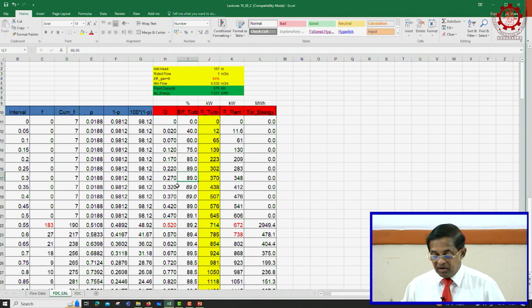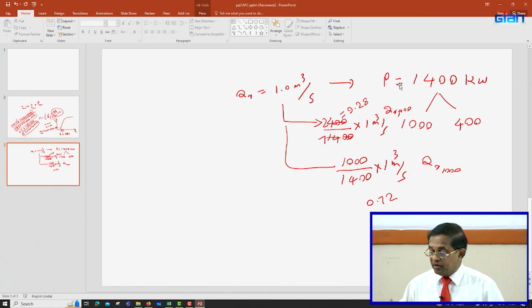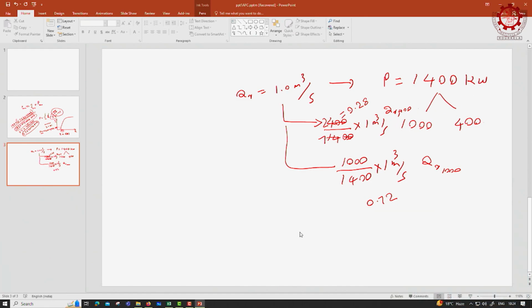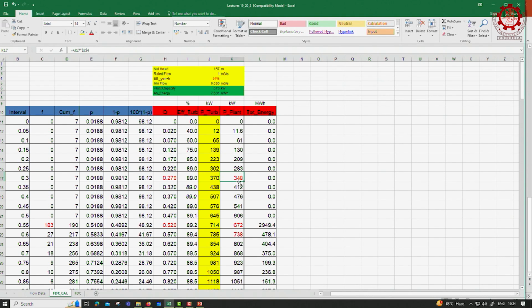So, its capacity is say until 0.32 or whatever, 0.27, 350 kilowatt is the machine capacity, because we approximated to 1400, right. Actually it is not exactly that, but in the calculation it is shown as 0.27 and 350 or 348. Here we took it approximately. We have approximated to 1400 and 1000 machine and 400 machine, but in the calculation it comes as 348, because that approximation is not applying here, right. It does not matter for the calculation we use like that, but when you buy the equipment you have to use round values, 1400 kilowatt and so on.